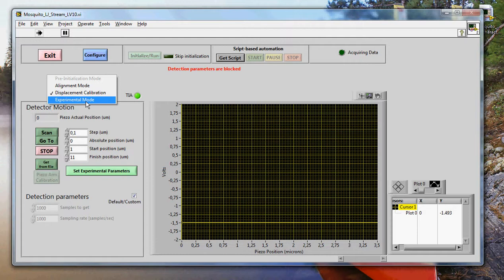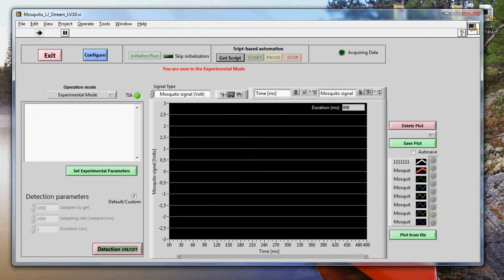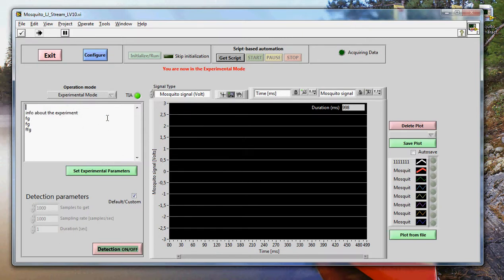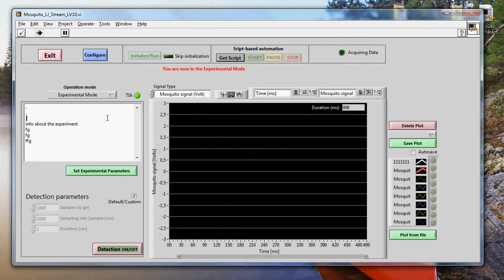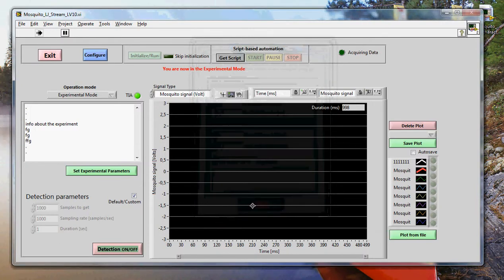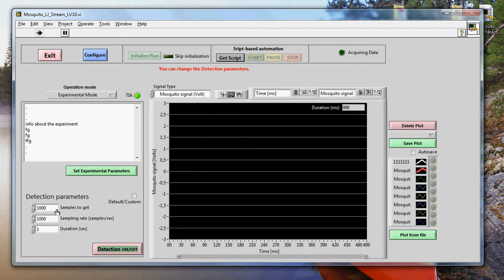So that's about the displacement calibration. We now go to the experimental mode. This is the mode where you will acquire the actual data. What you see here is just a pad. We put info about the experiment. This info here is going to be saved with the data. So let me put some just for you to recognize it later. You can again set the parameters here, experimental parameters. Here you can choose the detection parameters. This is very important.